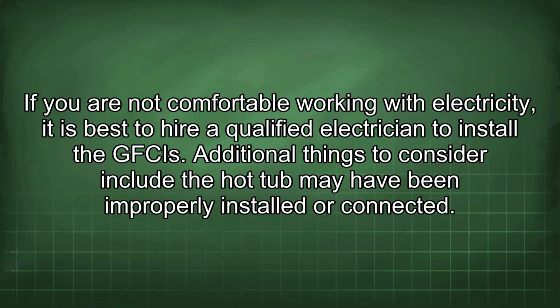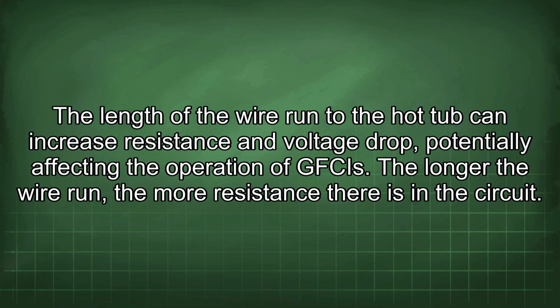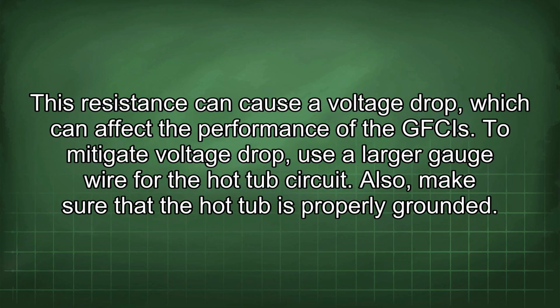Additional things to consider include the hot tub may have been improperly installed or connected. The length of the wire run to the hot tub can increase resistance and voltage drop, potentially affecting the operation of GFCIs. The longer the wire run, the more resistance there is in the circuit. This resistance can cause a voltage drop, which can affect the performance of the GFCIs. To mitigate voltage drop, use a larger gauge wire for the hot tub circuit. Also, make sure that the hot tub is properly grounded.